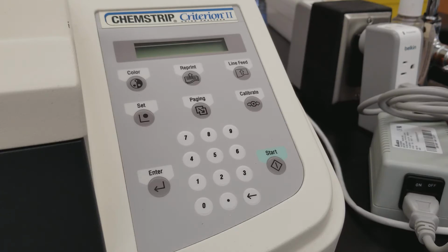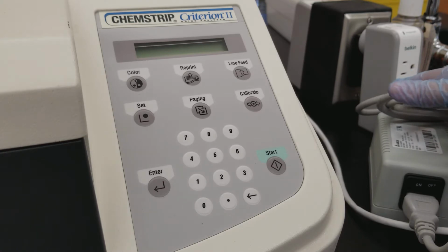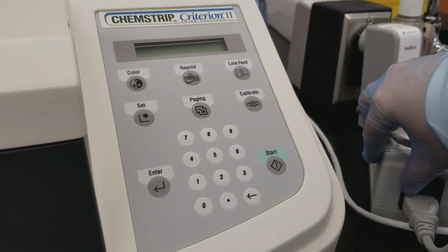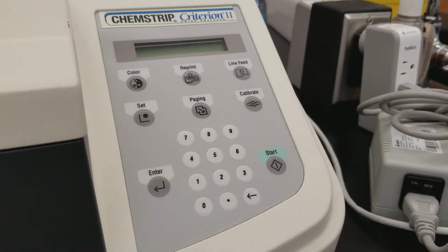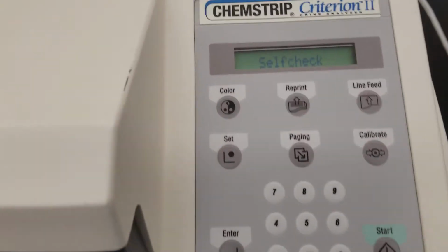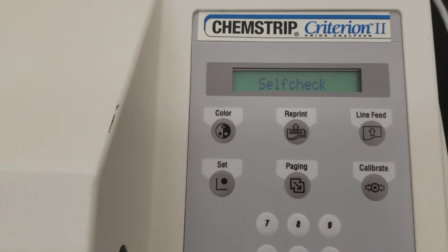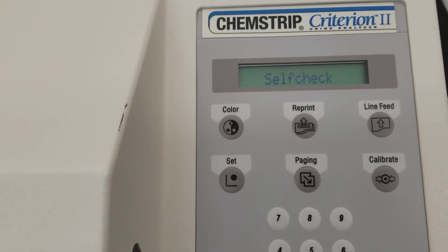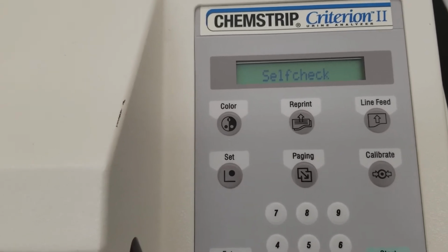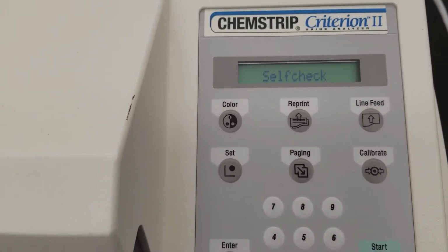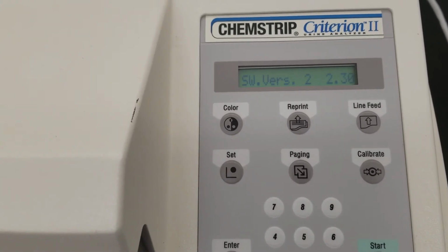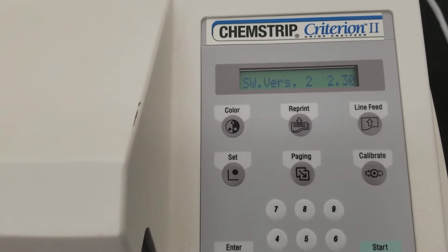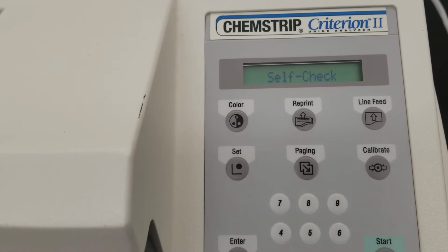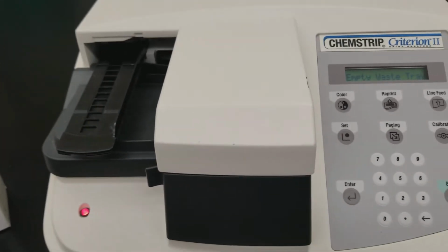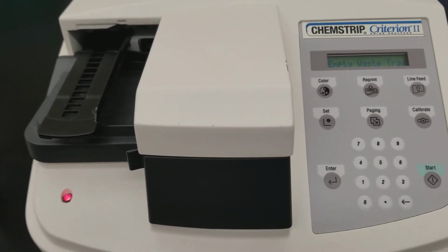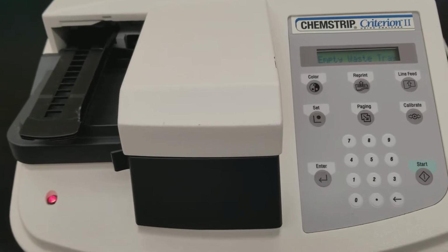When you turn it on, even though it's plugged in back here, you still need to flip this on switch. And then you're going to notice that it does its own self-check, and it will tell you what to do afterwards. Before we can do anything, it is going to have us calibrate. So we're running through a couple of screens here. It's self-checking. The light is red, so that means that it's not able to be run yet.